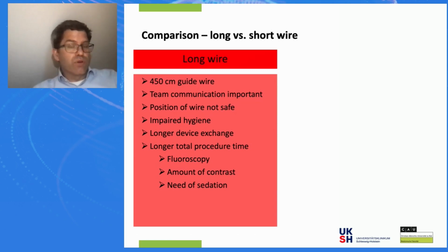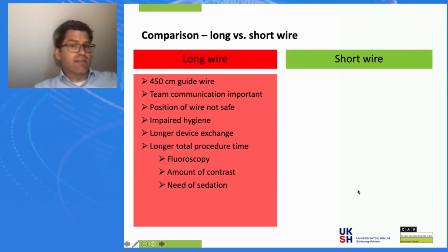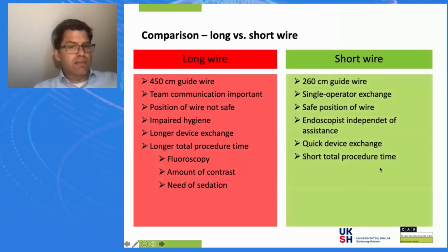And then actually vice versa is the short wire system. So we have a short wire, it's almost 2.60 meters. We can perform a single operator exchange by this locking device that's either connected to the proximal part of the working channel or to lock it at the distal part of the endoscope. We have a very safe position of the wire, and the endoscopist is more or less independent of the assistants. And that translates into a quicker device exchange and therefore a shorter total procedure time.